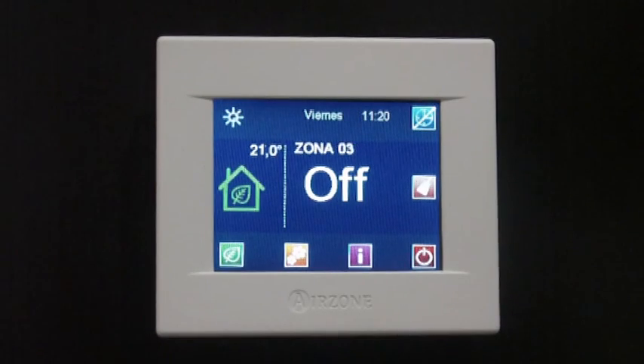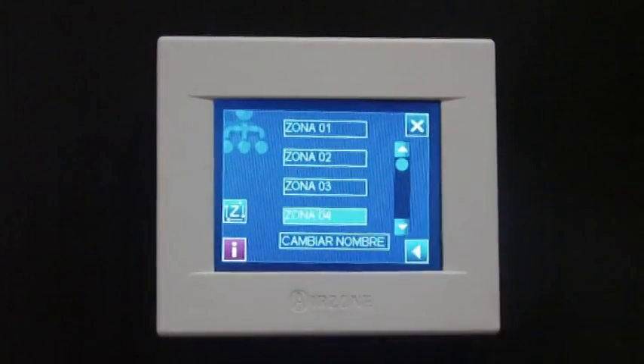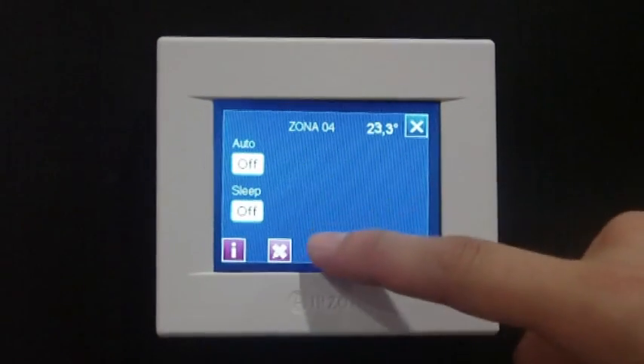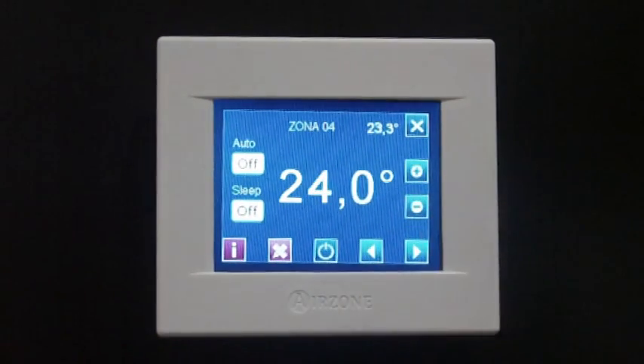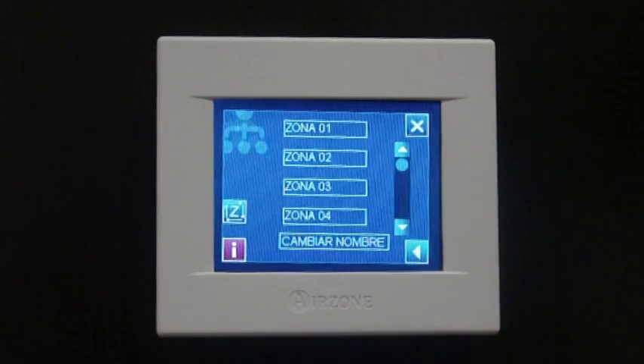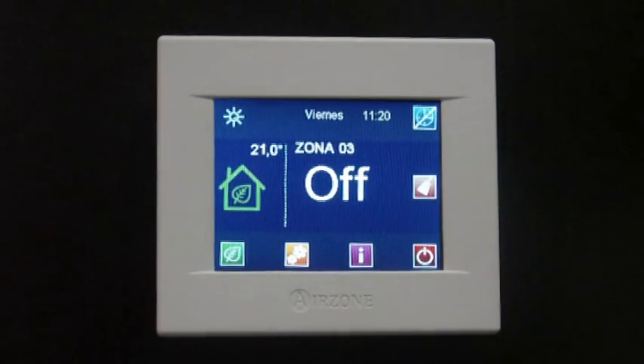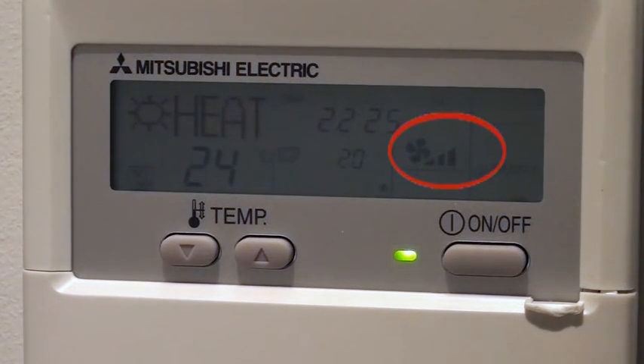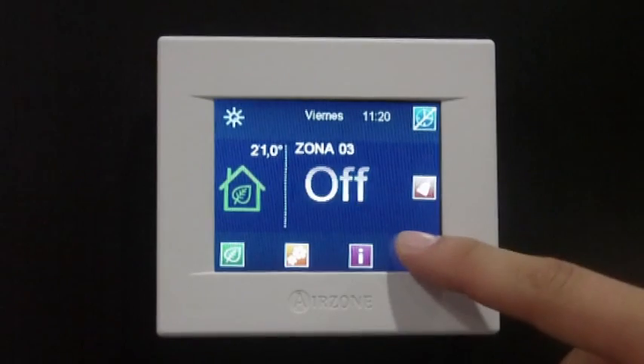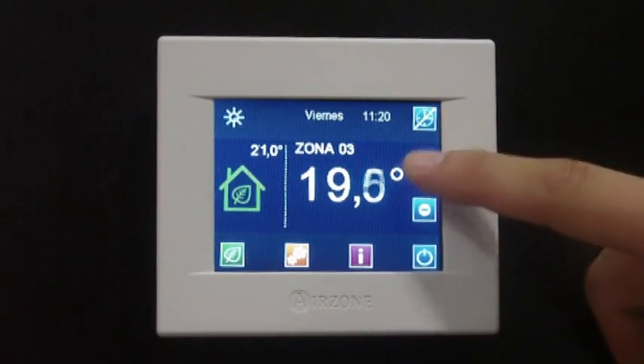The Air Zone communication gateway also sets the indoor unit fan speed so that the performance of the system is adjusted according to the dynamic behavior of the installation. When there is one zone in demand, the system will set the indoor unit fan speed to the minimum available. If the number of zones on demand increases, the indoor unit fan speed will increase accordingly.